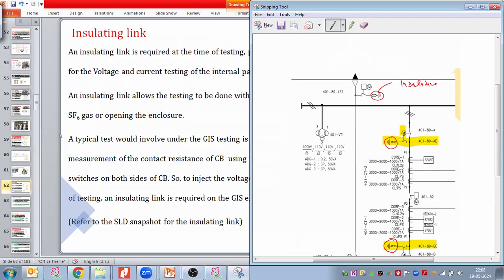It is the insulating link, which is 10 kilovoltage rated. Whether it is required or not required, please, when you prepare the SLD, make sure that each and every maintenance earth switch has this kind of facility. Please indicate this in the SLD as well, because I have seen so many SLDs, the engineers are preparing the SLD for the GIS subsystems, and they do not indicate this insulating link. They just prepare the SLD without link, directly grounded.